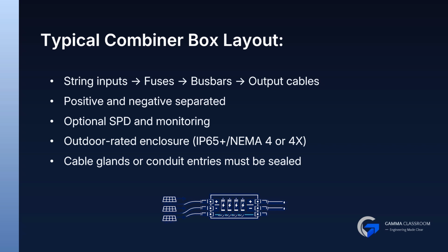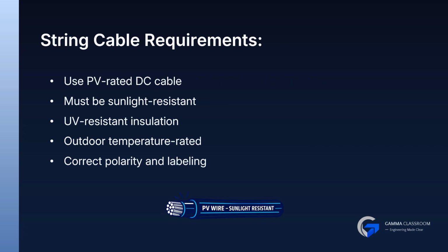Combiner boxes are outdoor rated and designed to handle harsh conditions. PV string cables must be sunlight resistant and UV rated because they are exposed outdoors for decades. These cables are designed to handle high temperatures, constant sunlight, and long-term weathering. Proper polarity and labeling are essential for safe installation and maintenance.